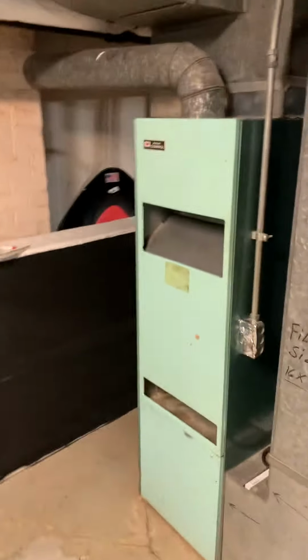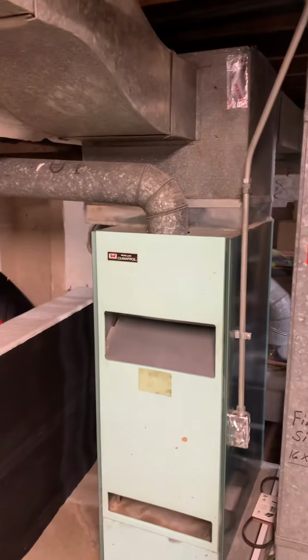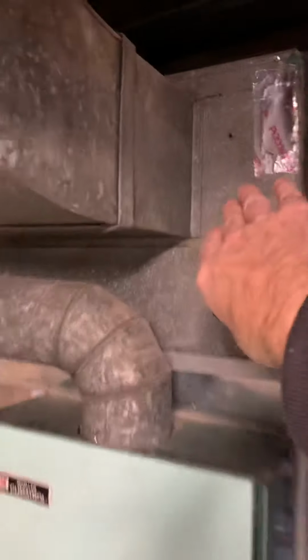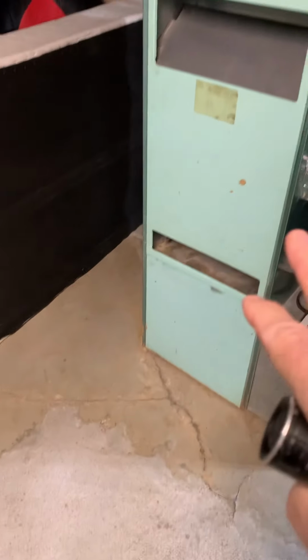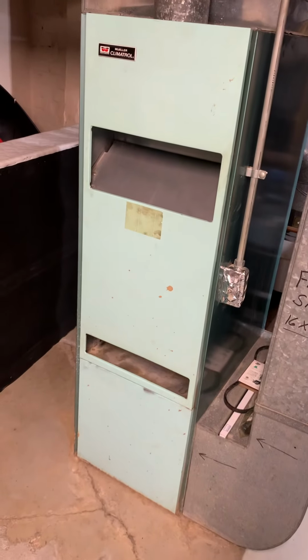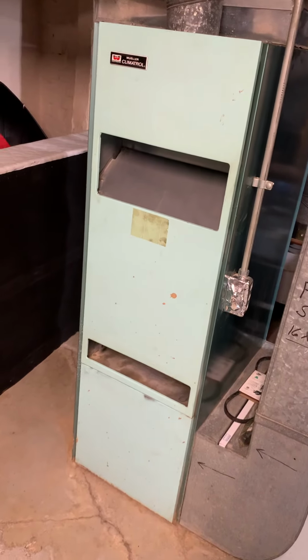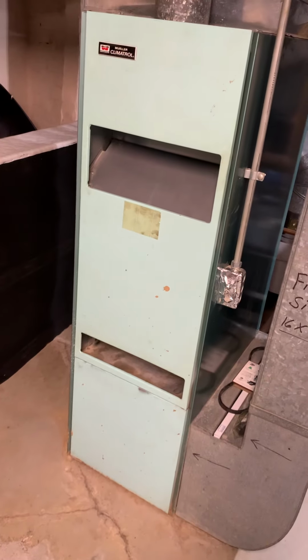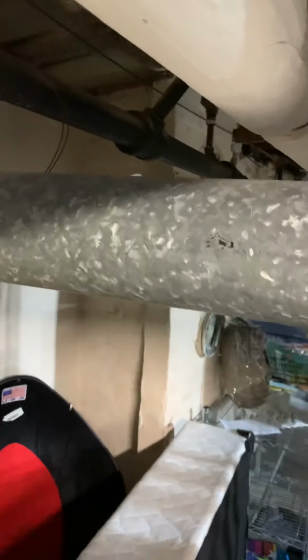And then the existing system, so this does first floor, got a coil that's really into the ductwork already and needs to be lowered down. A furnace that hasn't been turned on since the homeowners moved in. Be kind of leery of that, especially the heat exchanger. Look at replacing the return air drop. The flue piping runs over and goes out through the chimney.